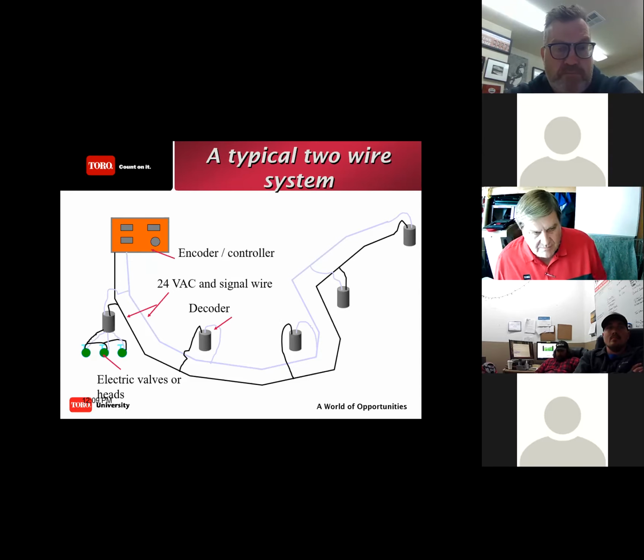On an AC system, you've got a hot wire and a common wire, and the common wire is unique because it goes to each and every single zone valve out there. On a 2-wire system, it's 2 wires, but they're polarized. Why? Because you've got the AC on there, but you also have DC communication. So polarity is very, very important.